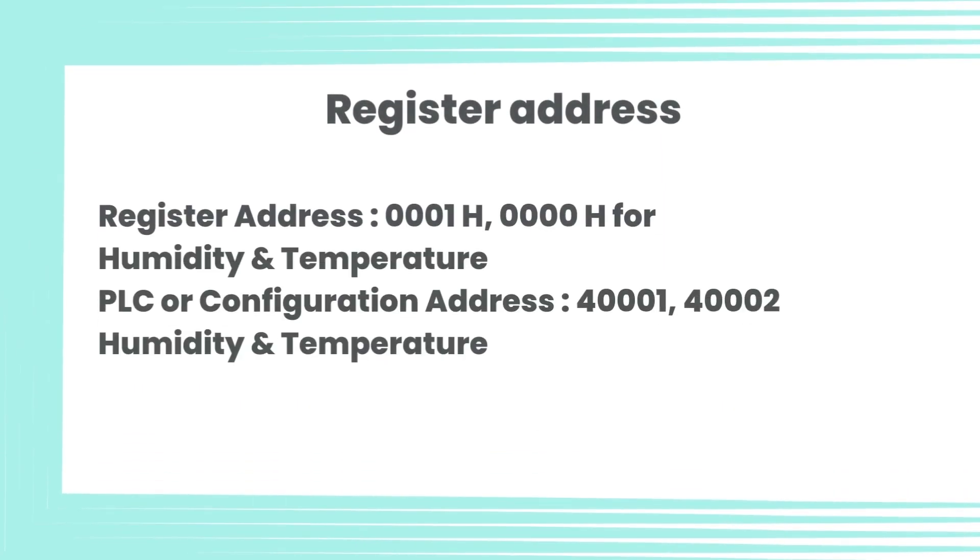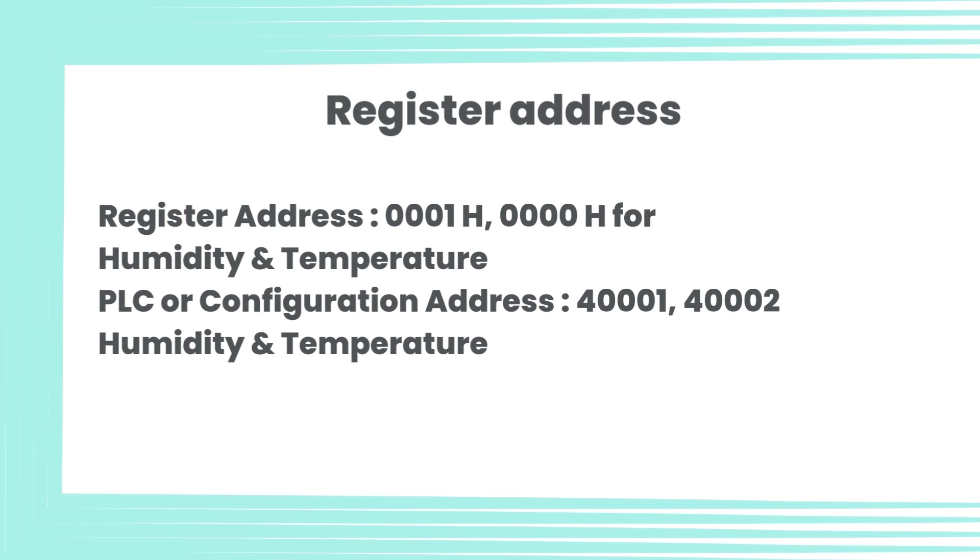Register address for this device is 0001H, 0000H for humidity and temperature. PLC or configuration address is 40001 and 40002 for humidity and temperature.